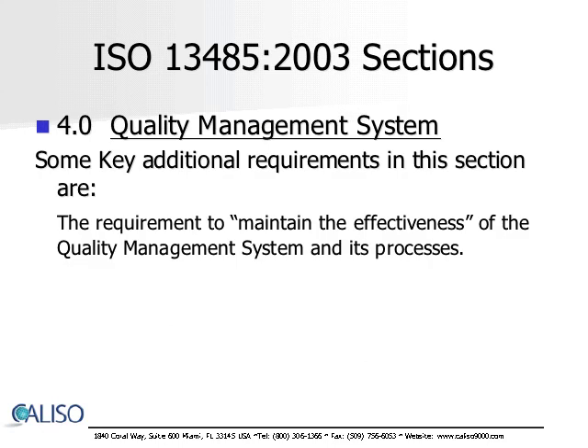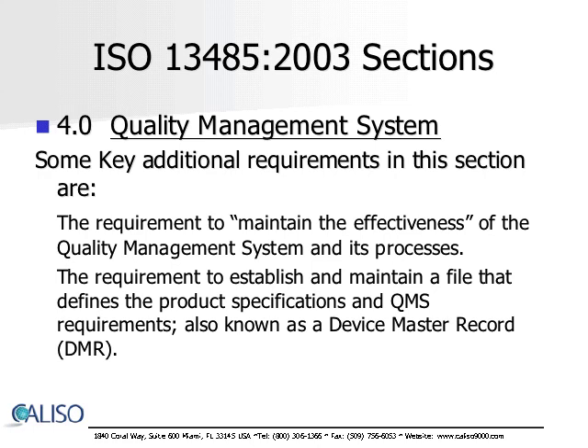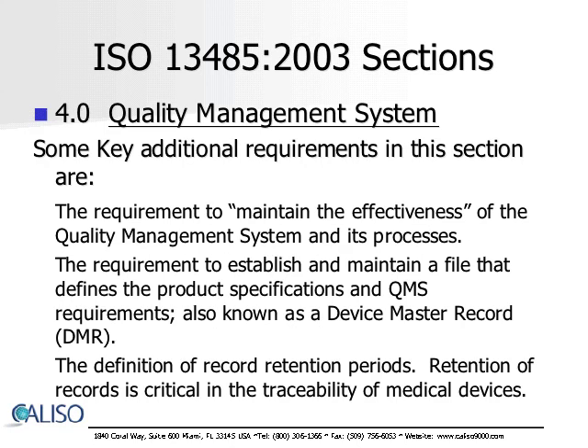Some key additional requirements found in this section are the requirement to maintain the effectiveness of the quality management system and its processes, the requirement to establish and maintain a file that defines the product specifications and QMS requirements — also known as a device master record or DMR — and the definition of record retention periods. Record retention is critical in the traceability of medical devices.